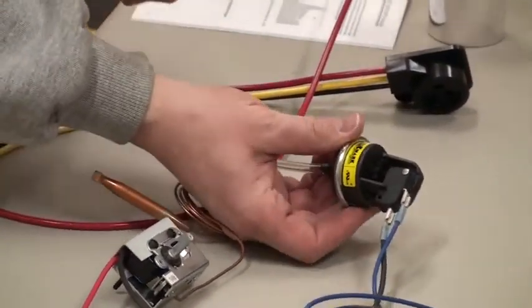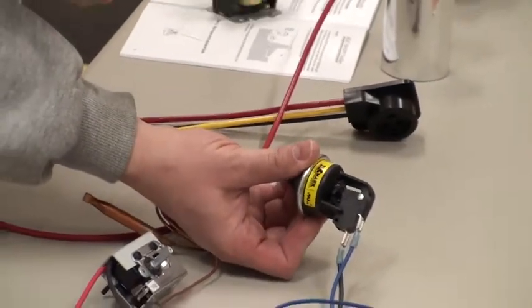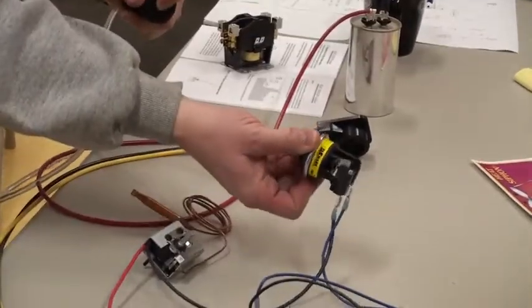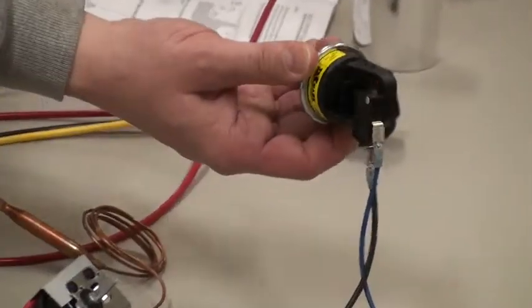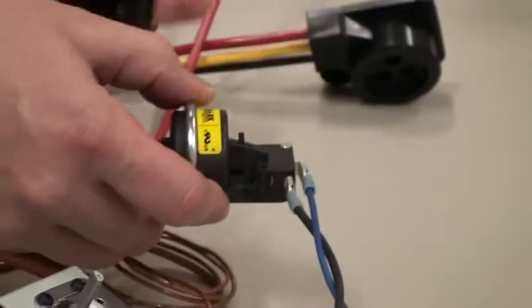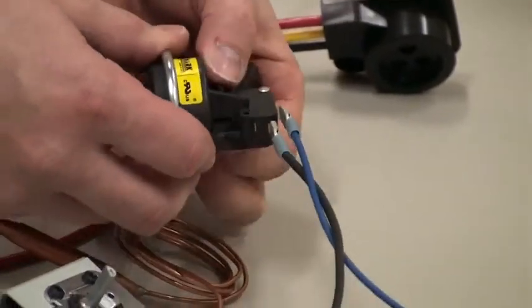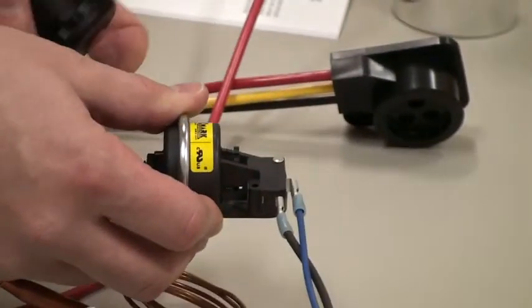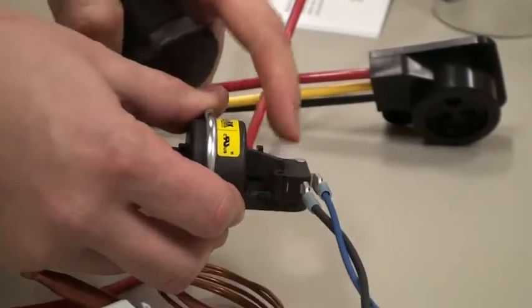Do you see the piston in the center moving up and down? It also doesn't have to be close. Can you see it? Yeah. There's a little nipple on the switch here. If there's enough pressure in the water, that will go up and actually activate the switch.